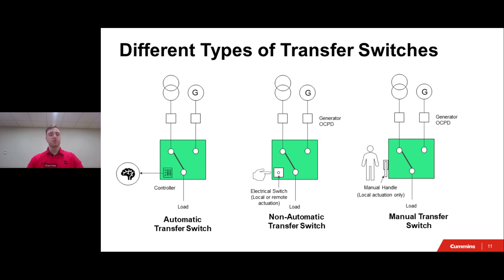So to start off this discussion, I will first go over the automatic transfer switch, which is that transfer switch all the way off to the left there on this slide. In this switch, you have a controller, and there is an autonomous function where the controller will monitor the quality and availability of the power source. Those power sources, once again, being your normal and emergency. And if needed, the control will decide when to transfer power from one source to another. A typical sequence of operation would look like your loads are being powered by the utility. Then there is an outage or a power disruption of some kind.